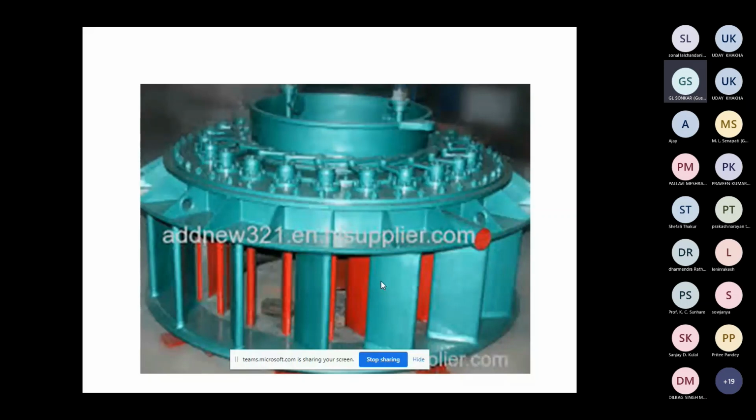The gap in between the blades of the runner will be closed or opened. The gap in between the runner blades gates the passage of water through the permission of your guide vanes. That means if the guide vane permits, then only water will enter the gap in between the runner blades. And the outer blades, these are the fixed blades in green color.